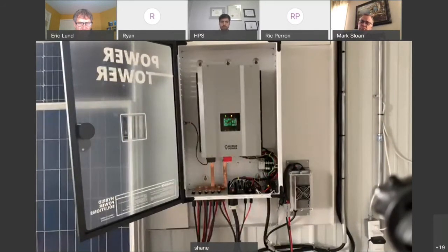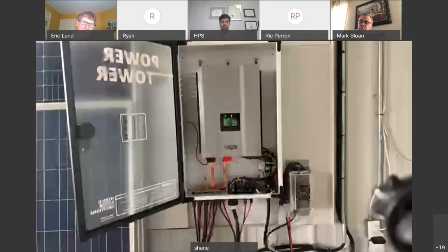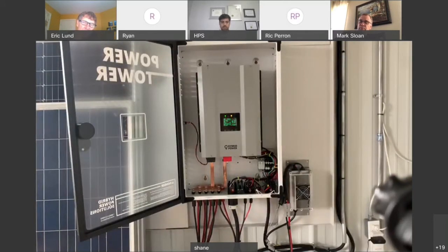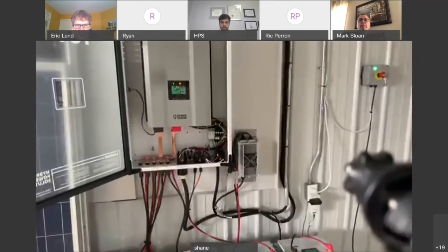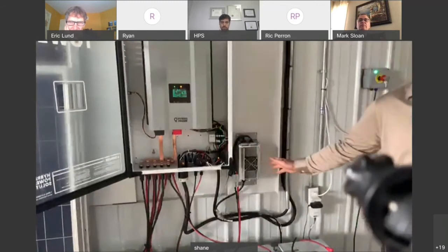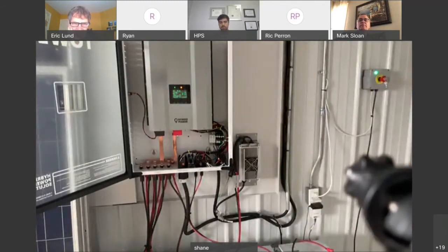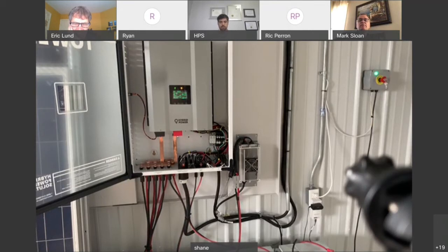Now, scenarios where you'll need additional charging. I had a 20 kilowatt propane standby generator as a charger and bypass carry-through, but standby generators burn just as much fuel at 20% load as at 60% load. They're made to handle a big surge, so the last thing you want is a generator running that you're not pulling much out of while it burns the same fuel. So what we can do here is add an additional DC charger pre-programmed for the lithium cells, giving another 3 kilowatts of charging. Now you could charge a larger bank quicker while the generator is running. You don't need that unless you have more than 3 to 4 modules on your battery bank, since the charger on the power tower is big enough to handle about that much.